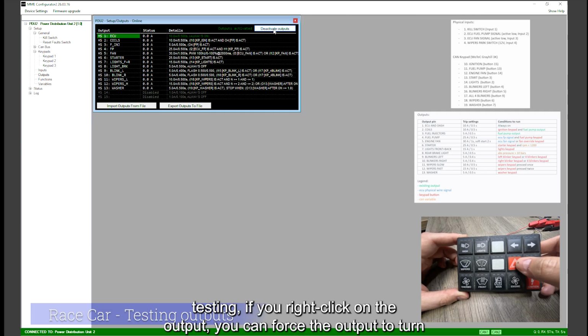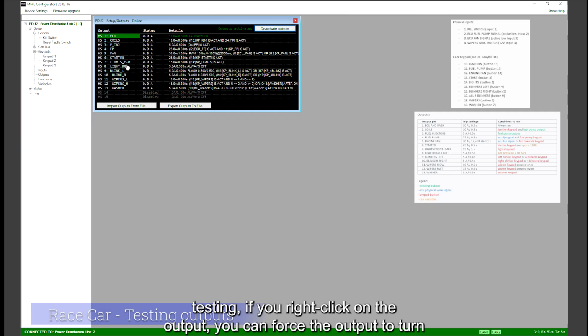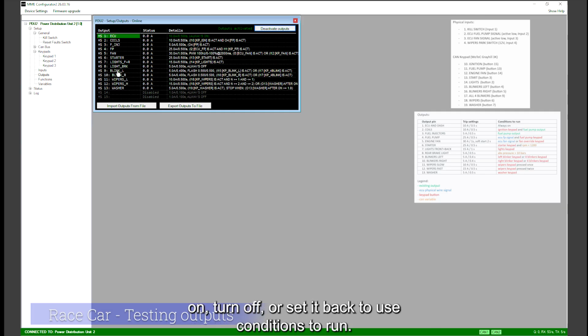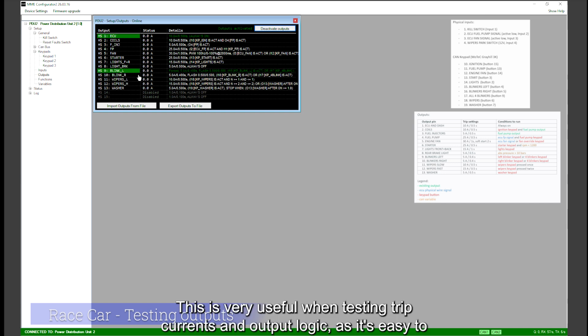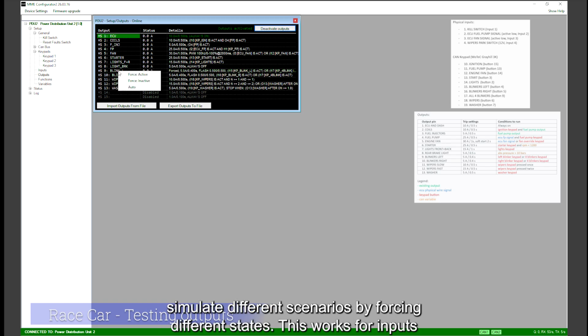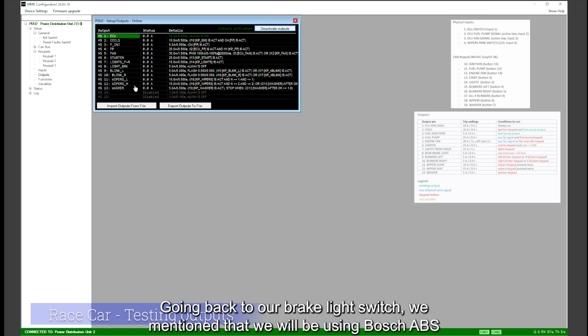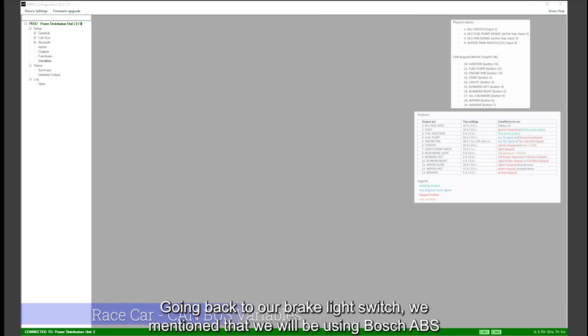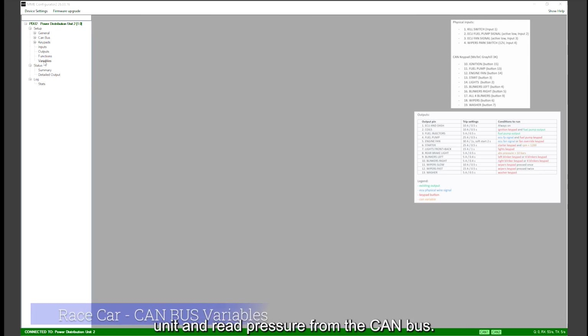When testing, if you right-click on the output, you can force the output to turn on, turn off, or set it back to use conditions to run. This is very useful when testing trip currents and output logic, as it's easy to simulate different scenarios by forcing different states. This works for inputs and functions too. Going back to our brake light switch, we mentioned that we will be using a Bosch ABS unit and read pressure from the CAN bus.